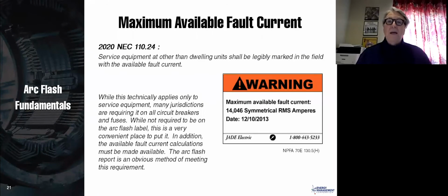All right, 2020 NEC 110.24. Service equipment other than dwelling units shall be legibly marked in the field with the available fault current. So this is a new requirement, and I believe it was new in the 2017 version of NEC, but it hasn't been out for too many years. So the code says that on the service equipment, and only the service equipment, you have to have some kind of a sticker that says what your available fault current is.